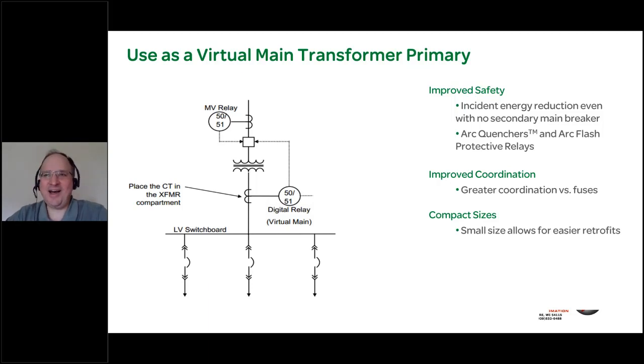And the economics of switchgear has really changed over the past 5 years. Low voltage breakers continue to get more expensive, but medium voltage breakers, due to the dramatically decreased size and new materials used in MV breakers, have actually gone down in price. So by eliminating the secondary physical main, and we have a completely separate presentation on secondary virtual mains, so it's not my purpose in this presentation to recap all the advantages of secondary virtual mains. But the bottom line is this hybrid switchgear is the right solution on the primary side of the transformer.